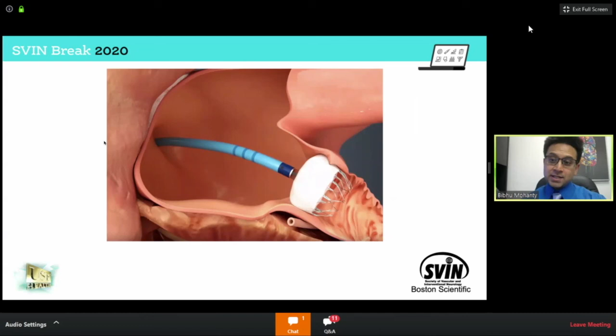The device can be captured. So if we feel that the device is too deep or too superficial, it can be recaptured fully. It can be recaptured partially. We can take the entire device out after recapture and put in a different device if we feel like one of the sizing needs to be adjusted. And that is done fairly commonly. Again, as I mentioned in the beginning, this device tends to be oversized because we want it to be compressed within that appendage so that it's secure and it's not going to move. And then it has those 10 anchors around it that allow it to stay fixated within the left atrial appendage.